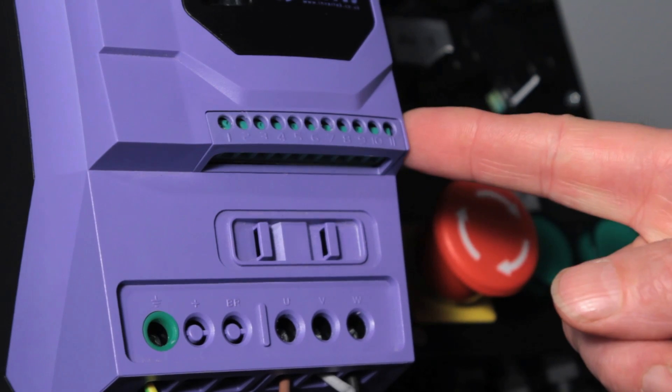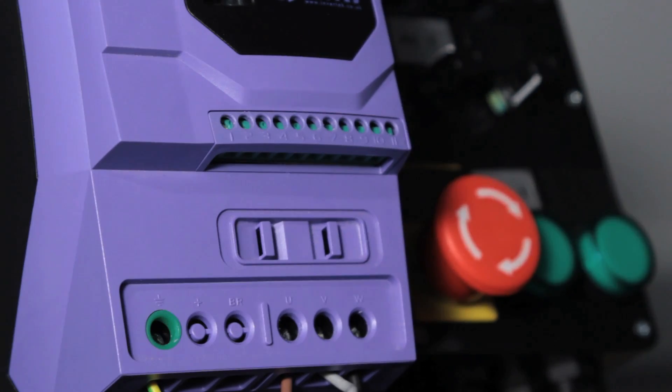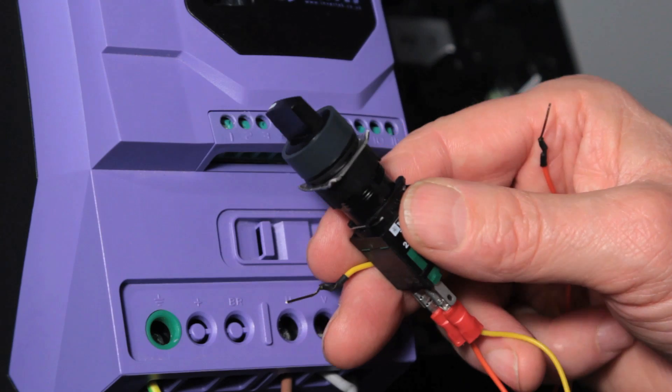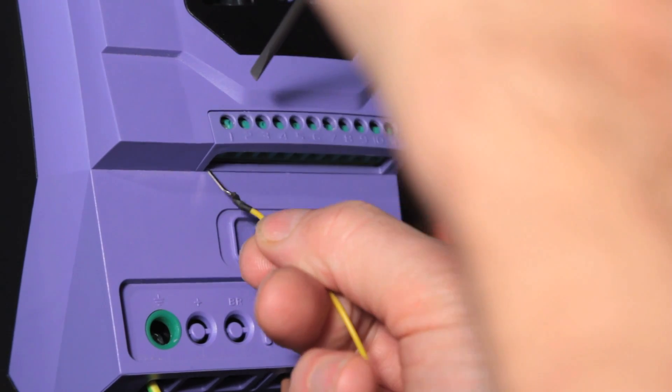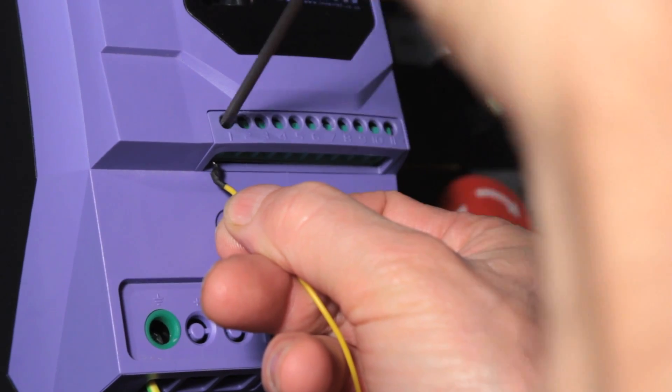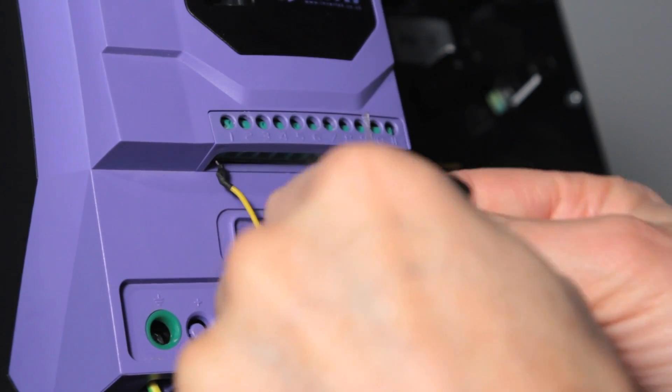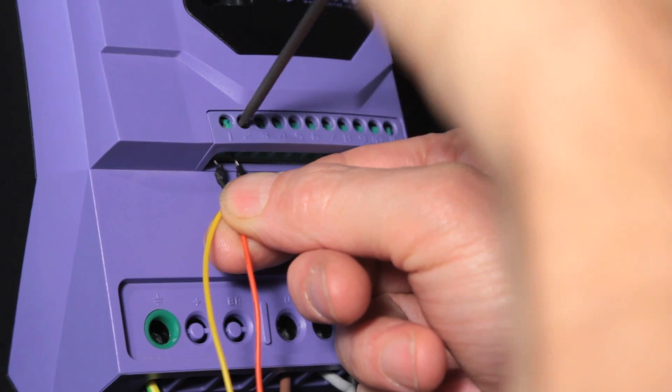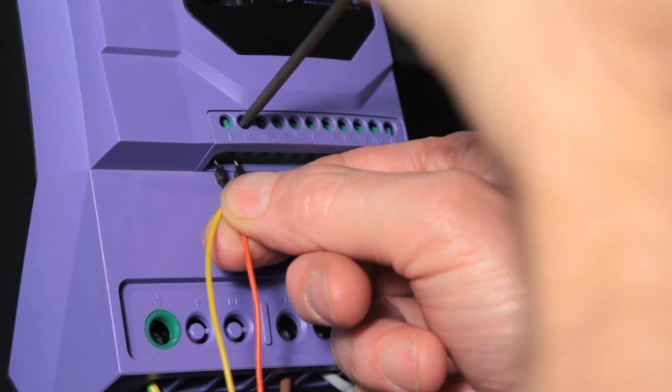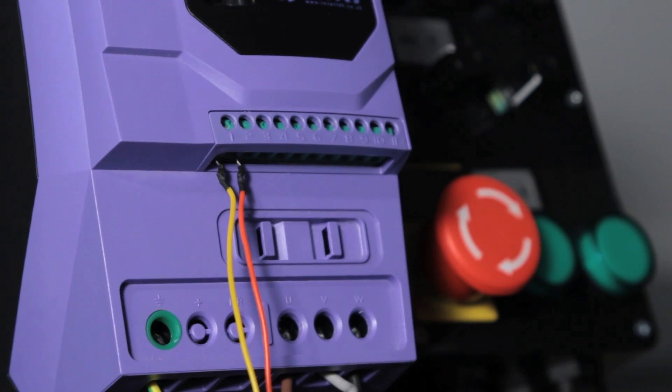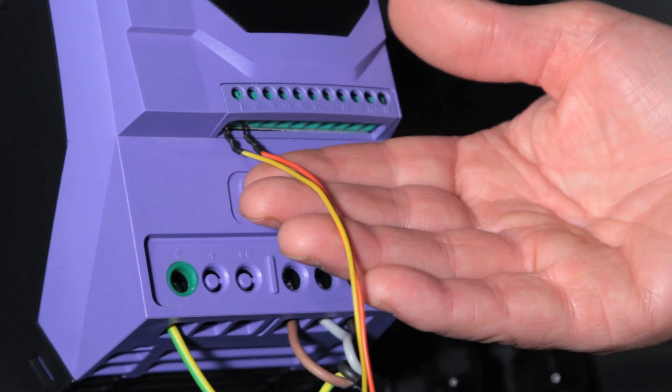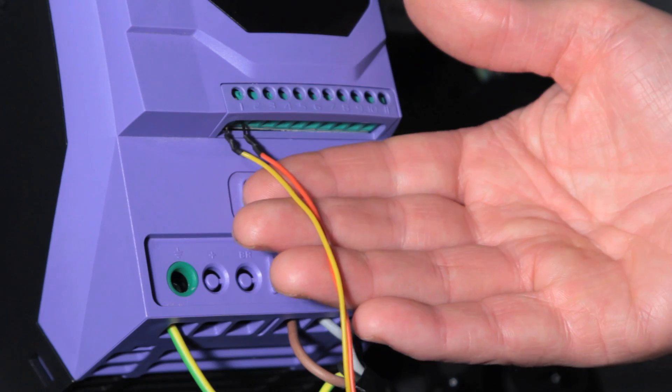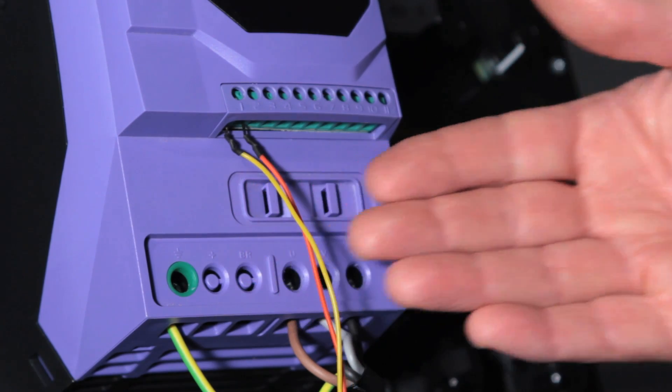Now for the control wiring. Connect an enable switch to terminals 1 and 2. I'm using a loose switch so you can see what's going on. You always need to make this connection even if you are controlling the drive from a built-in panel. A simple wire link can be fitted in this case.